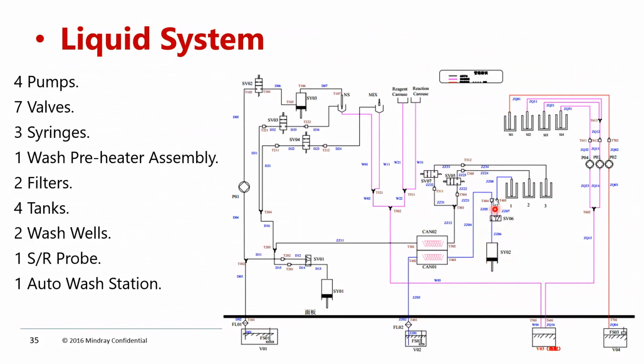So syringe 02 is only for dispensing the detergent. If cuvette washing is not happening properly, you have to check syringe 2 and syringe 1. This syringe will dispense the water through the preheater assembly. Here there are two valves, one valve for each probe. Probe number 2 is connected to valve number 5. Probe number 3 is connected to valve number 7.